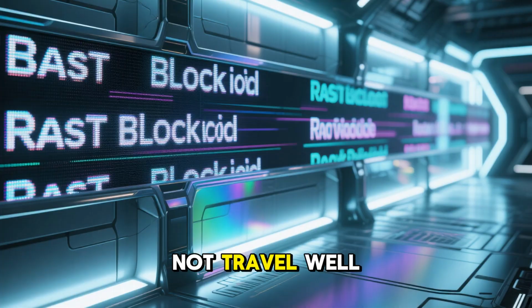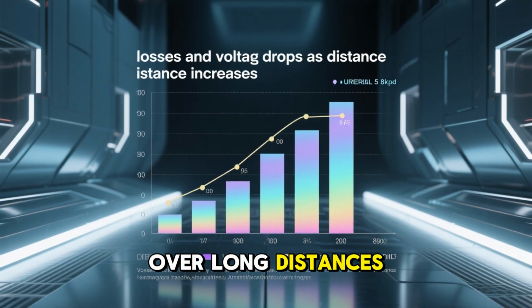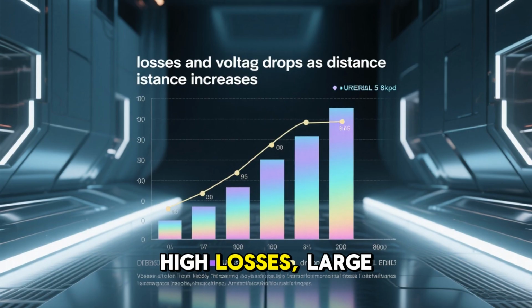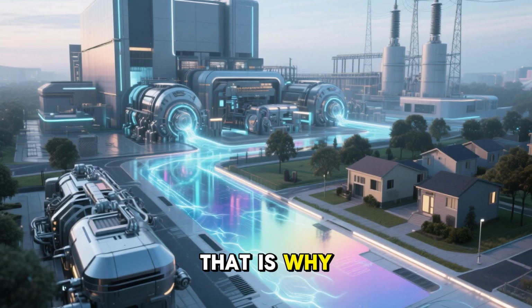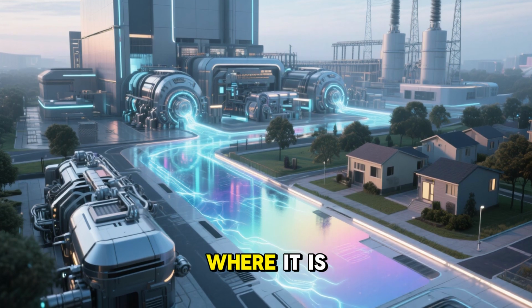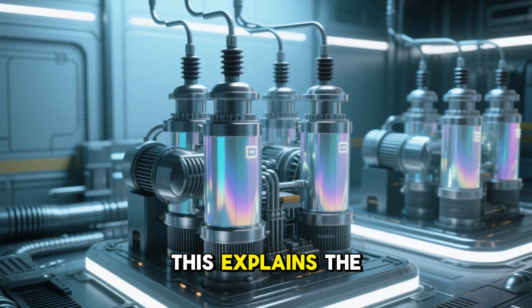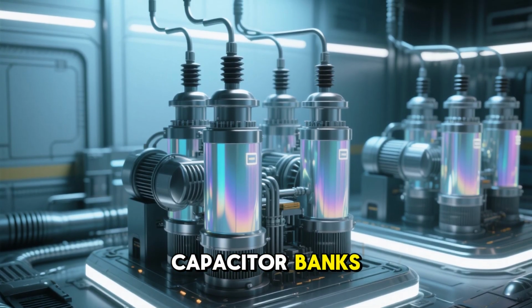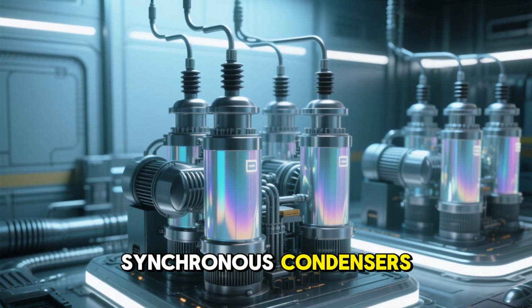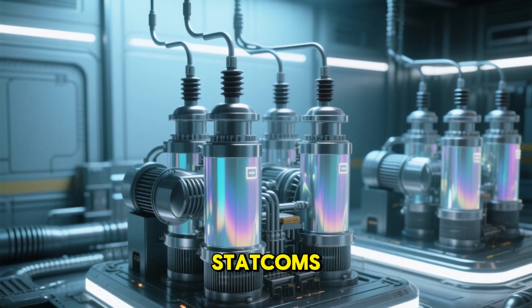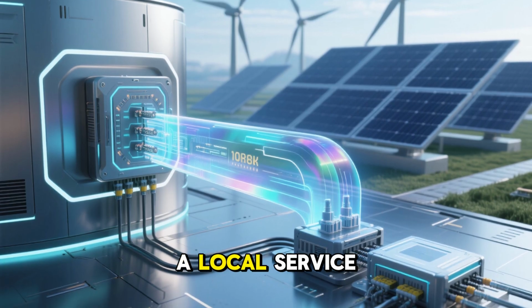Unlike active power, reactive power does not travel well. Trying to transmit reactive power over long distances leads to high losses, large voltage drops, and inefficient operation. That is why reactive power must be generated close to where it is consumed. This explains the widespread use of capacitor banks, synchronous condensers, and SVCs and STATCOMs. Reactive power is a local service.